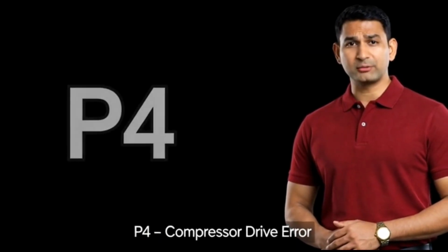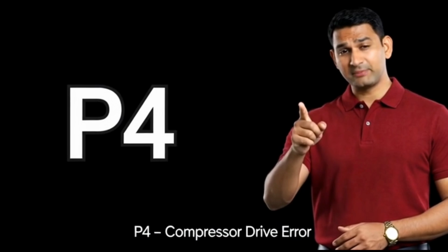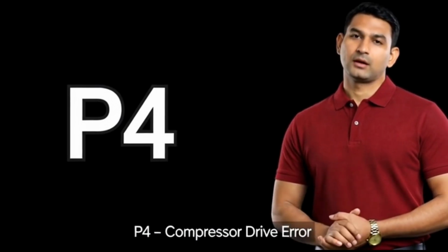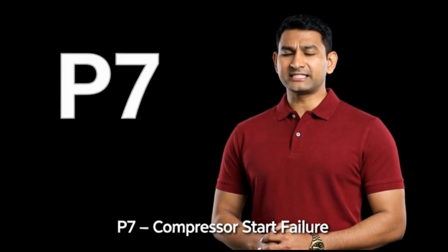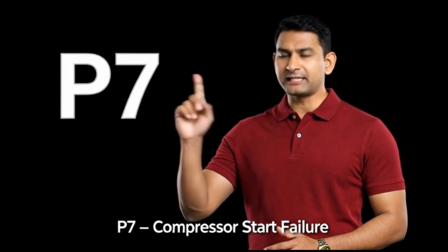P4 error shows compressor drive malfunction. AC may not start cooling. P7 error indicates compressor cannot start. Check PCB and wiring.